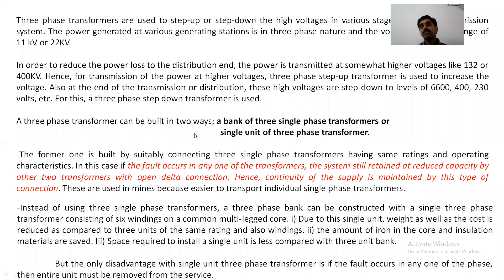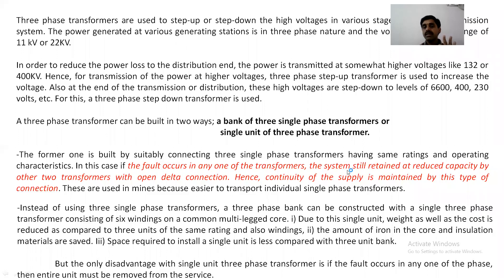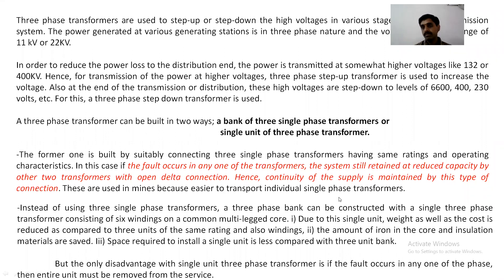The three-phase transformer can be built as a bank of three single-phase transformers or as a single three-phase transformer unit. Three single-phase transformers of the same rating and operating characteristics are taken to form a three-phase transformer. The main advantage is that whenever a fault occurs in any one transformer, the other two can supply the power — that is called open delta connection — so there is reliability and continuity of supply.